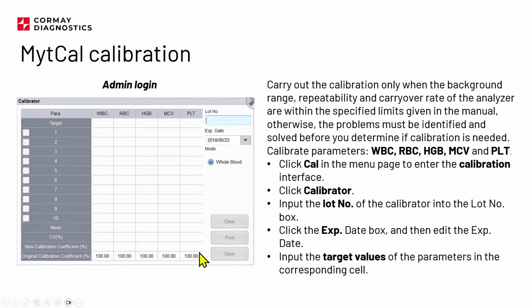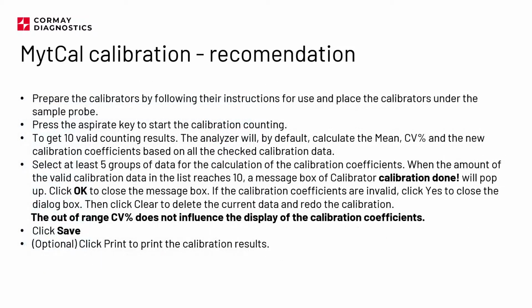So the calibration is, let's say, automatic, but you need to prepare the calibrator according to the instructions for use, mix it, present it to the sampling needle, and just press the aspiration button on the front panel of the analyzer, and make this 5 times. 6 times is up to you, but keep in mind the minimum is 5 times. And later we can save it.